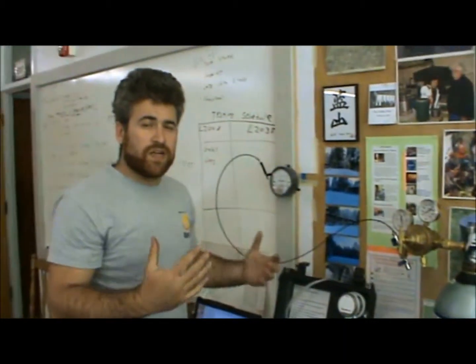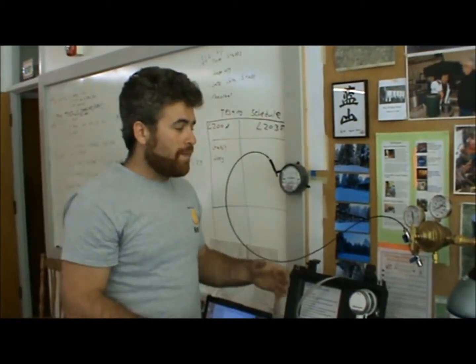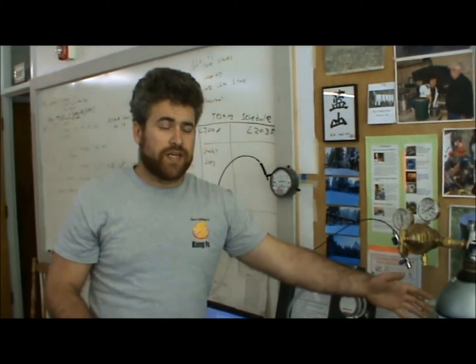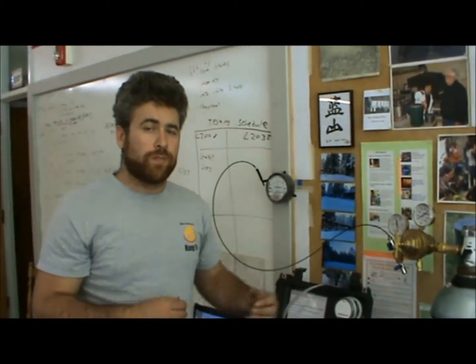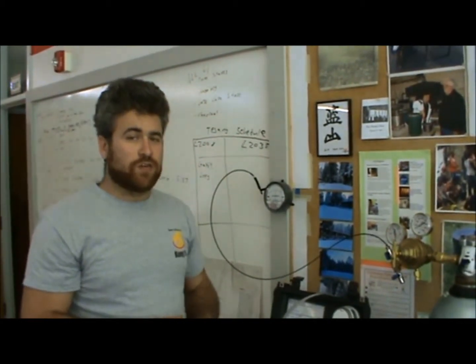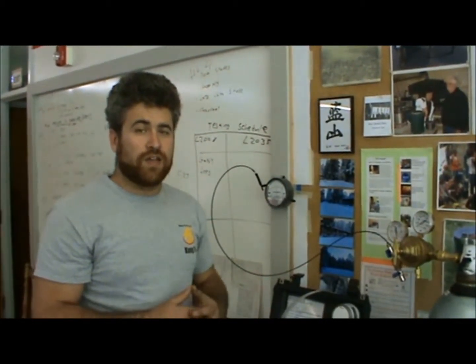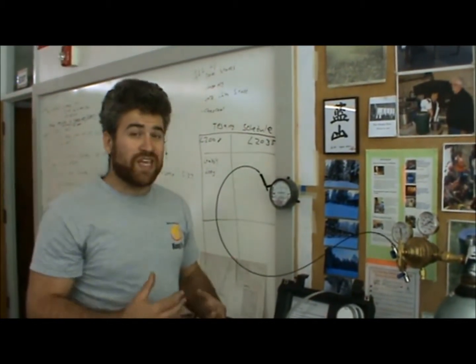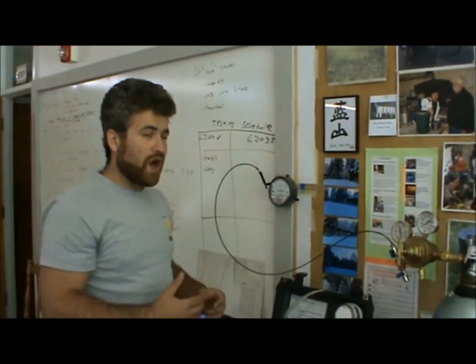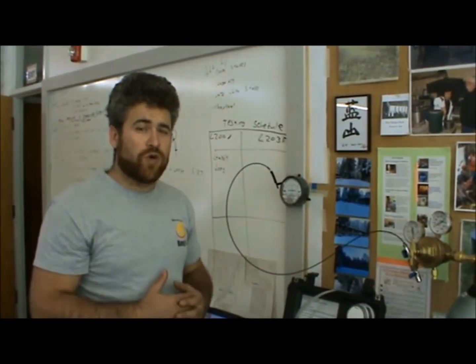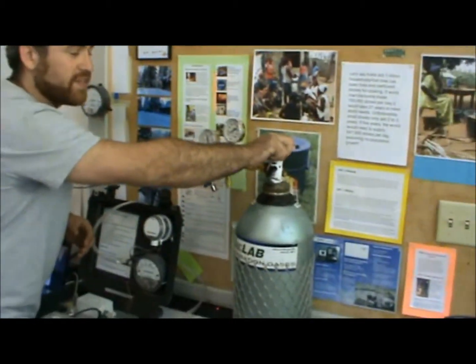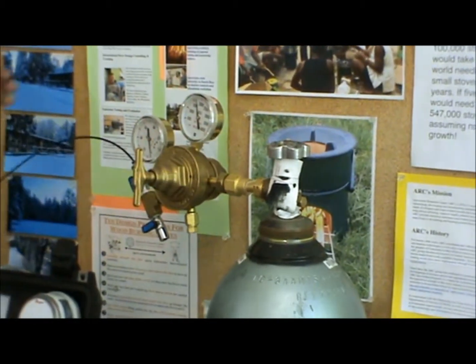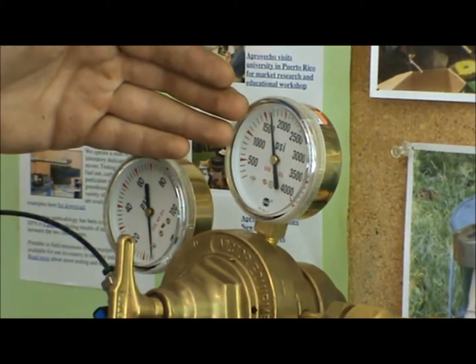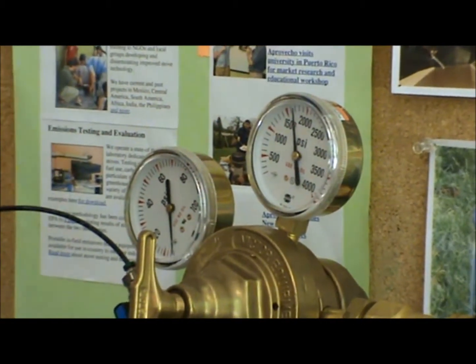It's very important to be in a nice, well-ventilated area because there is a little bit of carbon monoxide in here, and you do not want to fill your room up with carbon monoxide. We have some windows open. You can put a fan in, anything to ventilate the room a little bit and get some fresh air rolling so you're not breathing in that carbon monoxide. The levels of carbon monoxide have never been too high, but it's still something to be careful about. So I'll turn on my gas tank at the top. You'll notice our needle has jumped up here. It means that gas is flowing, and we can hear the gas flowing.